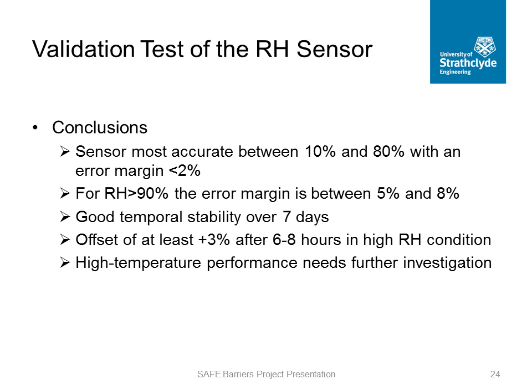As a conclusion of the first experiment, the relative humidity sensor is most accurate between 10% and 80%, with an error margin of less than 2%. As the relative humidity increases, the offset increases correspondingly, and for the relative humidity over 90%, the error margin is between 5% and 8%. That's the field that we'll focus on improving in our future work.